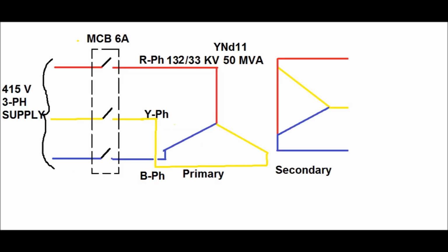Here the diagram has been shown for a magnetization current test for a YND11, 50 MVA, 132 by 33 kV power transformer. Here the secondary is delta connected and the primary is Y connected. The delta side is kept open, and in the primary side, that is the star connected side, a 3-phase 415 volt supply has been given through an MCB of 6 ampere rating.